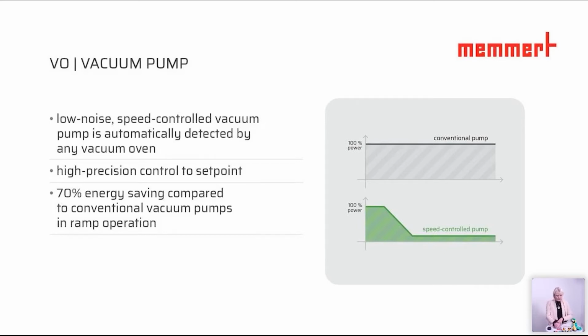Because what happens when you use a membrane pump? You normally have the membrane pump working at 100%, or let's say it's switched off whenever the pressure is reached. That is possible when you use the Memmert PMP model type. Then the pump is automatically switched off whenever the pressure is reached, and it will automatically switch on. But additionally now, we have this speed control pump, which means that the speed is adjusted in small steps. It is not always running at 100%. So it is a demand-oriented pump which is going to be used. This pump is from the company KNF.